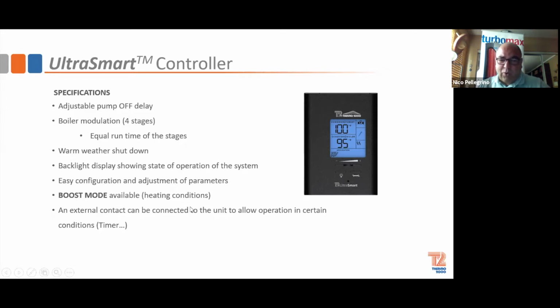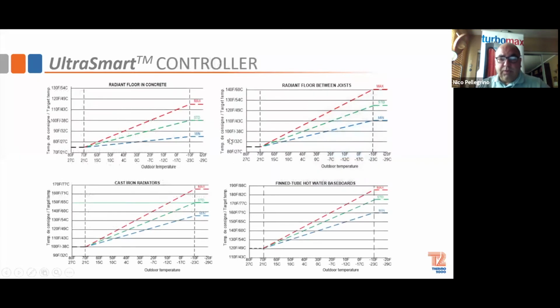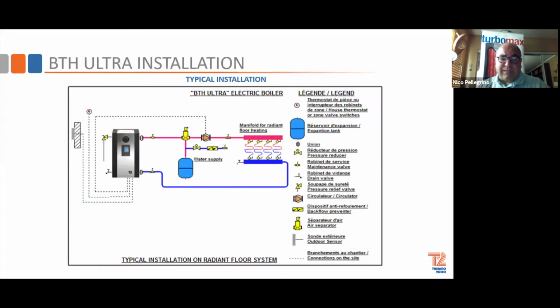There's also a boost mode available in the controller. We also have built-in parameters for outdoor reset. We built in curves, so if you're doing radiant in concrete, you'll have a specific curve for that, and it's all set. As I said, the BTH Ultra is in and out, and it comes with a relief valve and a drain valve. Everything else you have to purchase from the supplier.